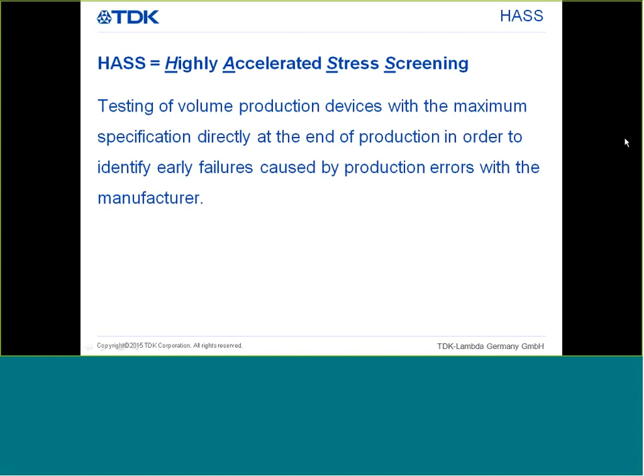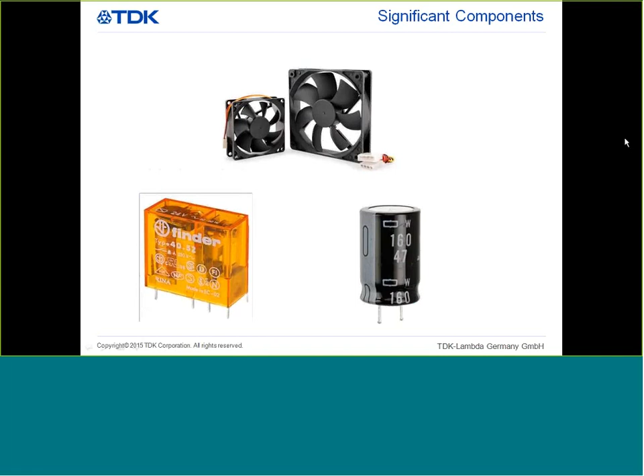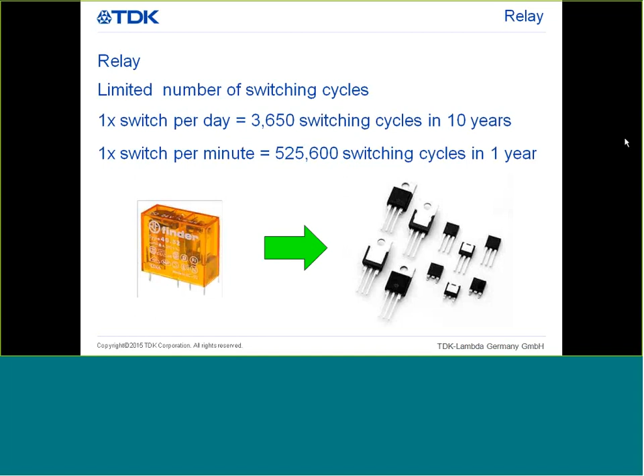For a developer of standard power supplies, the same components are always most responsible for the lifetime expectancy. Therefore, the focus should be placed on the fan, the relay, and most important, the electrolytic capacitor. So, the relay. Each relay has a defined number of switching cycles before the function reliability gets lost. This depends on the switching cycles per unit of time. Few switching cycles per year or a repeating operation per minute.